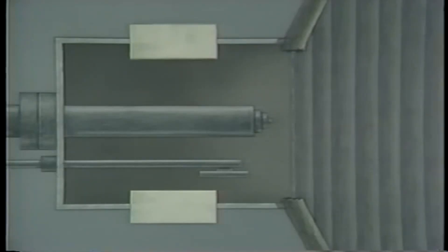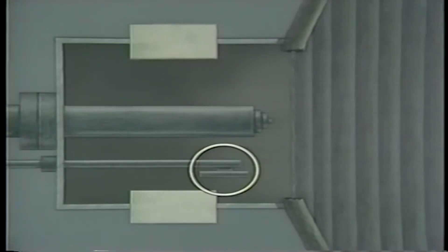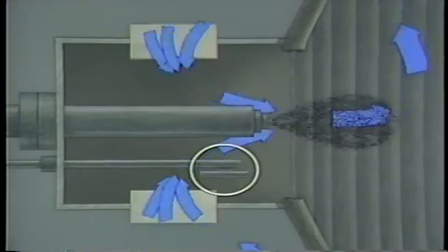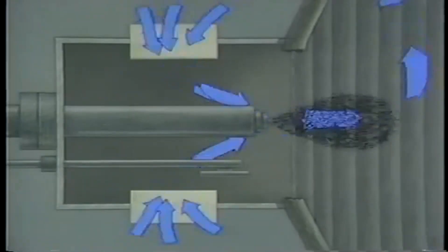However, boiler explosions occur during unusual conditions. Let's suppose that the igniter malfunctions and does not spark as it is supposed to. The operator turns the controller to start the igniter sparking, but in this case, the igniter is slow to respond and doesn't spark right away. The operator next establishes airflow to the burner port and then starts fuel flow. The igniter still doesn't spark. The air and fuel form a combustible mixture, and the mixture accumulates in the boiler as more fuel and air are supplied. If the igniter suddenly begins sparking, it will ignite this abnormally large mixture. The result is an explosion.